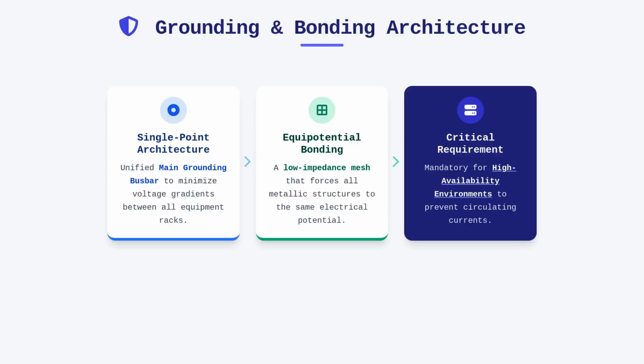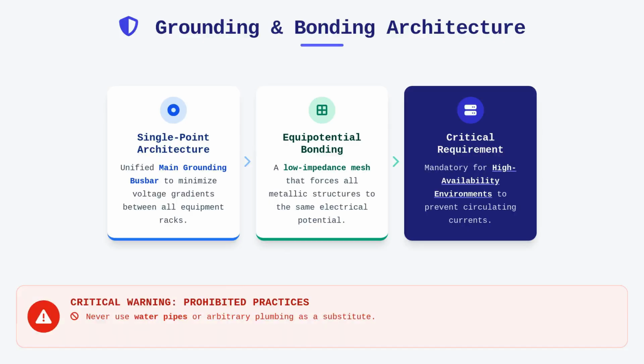Furthermore, one must never rely on arbitrary metallic infrastructure, such as water pipes, as a substitute for a properly engineered telecommunications bonding backbone. Using plumbing for grounding is not only a violation of the National Electrical Code, but also introduces unpredictable earth paths that introduce new, uncontrollable loop potentials into the sensitive signal environment.